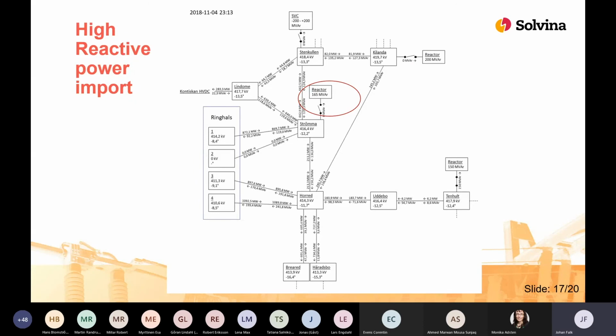Now I will carry on talking about one of these situations where Ringhals is absorbing a lot of reactive power. And here we can see that it's almost the opposite of the previous slide. Ringhals is importing reactive power with two of these reactors being disconnected. We can see it might have been more efficient if reactors would have been connected instead, especially the one at Strömma that is highlighted in the picture.